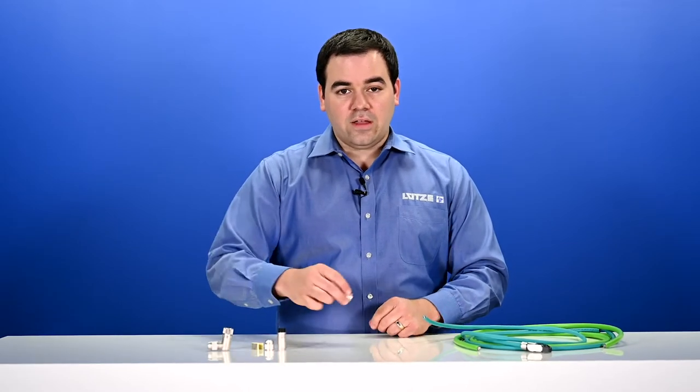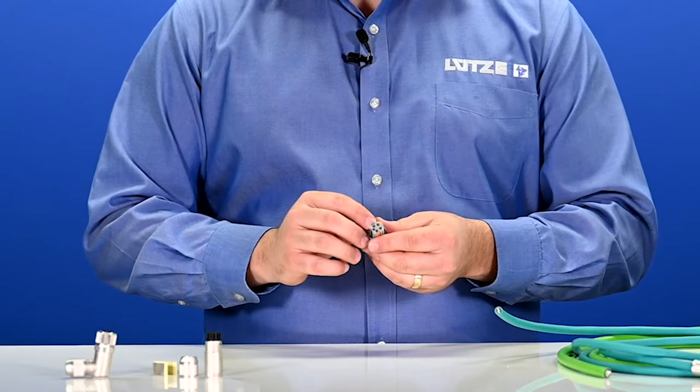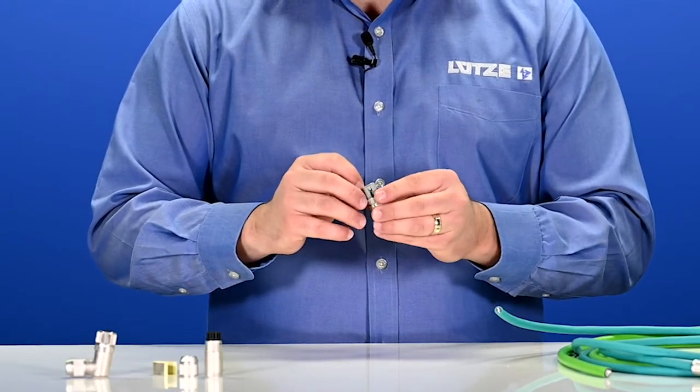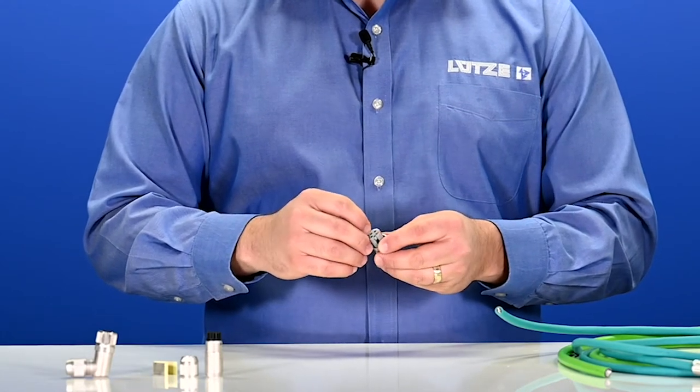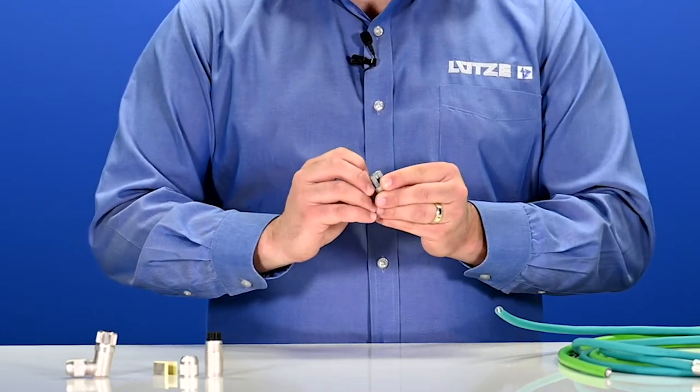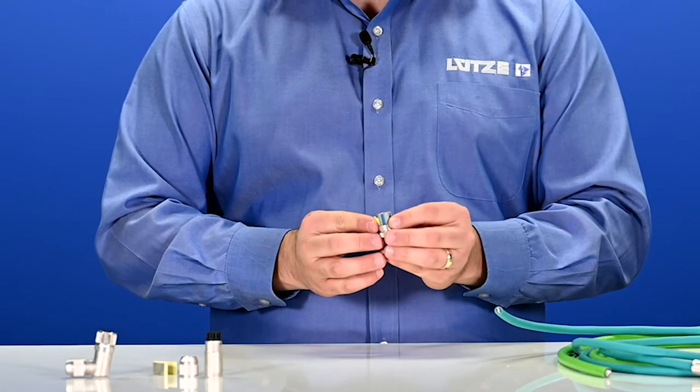The first thing that I'd like to point out about these connectors is that unlike most traditional M12 connectors, these don't use a screw type termination. These actually use a cage clamp design that opens up very easily with nothing more than a fingernail and allows you to make a vibration-proof connection to that terminal.